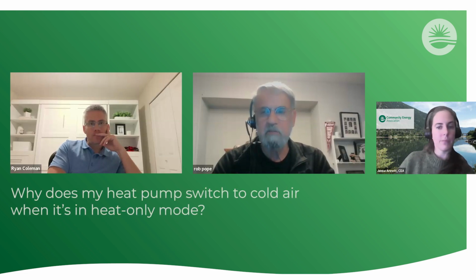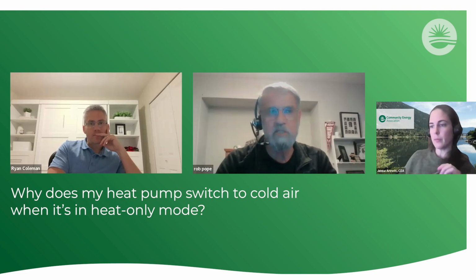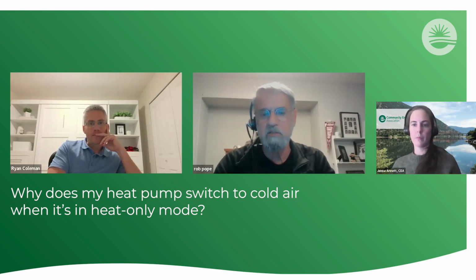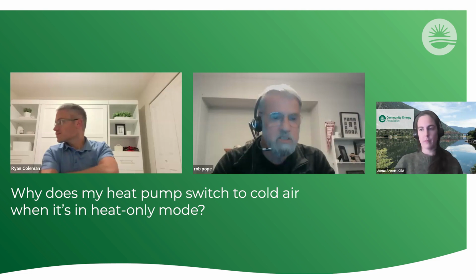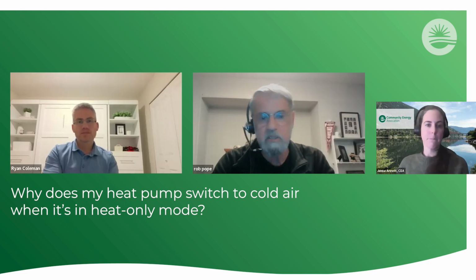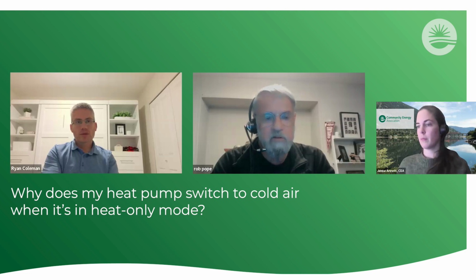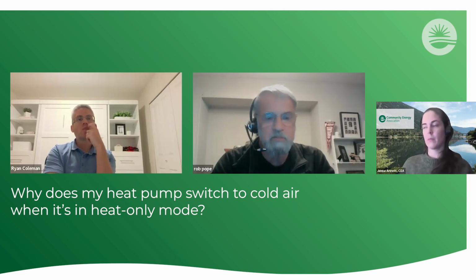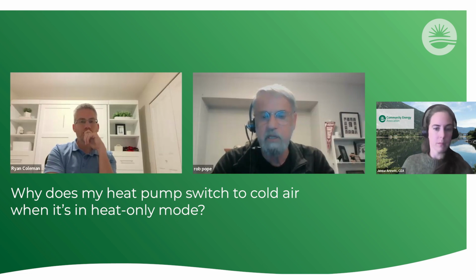So she's just trying to understand what's happening there and if there's anything she can do to avoid this and preserve any free heat that comes into the home environment rather than spitting out cold air. Yeah, if it's in heat mode, it should not be spitting out cold air unless it's in auto changeover mode or auto mode, because the thermostat will sense that the temperature has been satisfied if that's what's happening. If the ambient, solar gain for example, is ramping up the temperature beyond the set point, the thermostat sensor should note that and say we're happy.